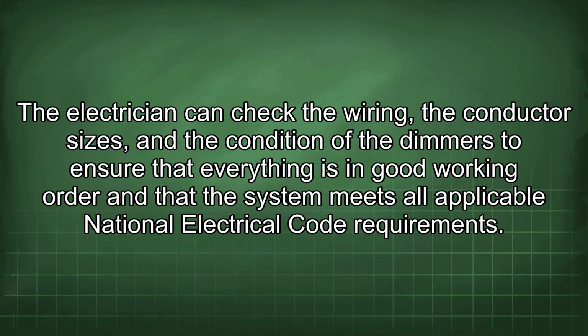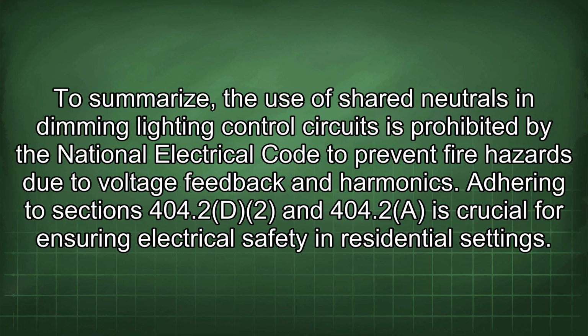The electrician can check the wiring, the conductor sizes, and the condition of the dimmers to ensure that everything is in good working order and that the system meets all applicable National Electrical Code requirements. To summarize, the use of shared neutrals in dimming light and control circuits is prohibited by the National Electrical Code to prevent fire hazards due to voltage feedback and harmonics.